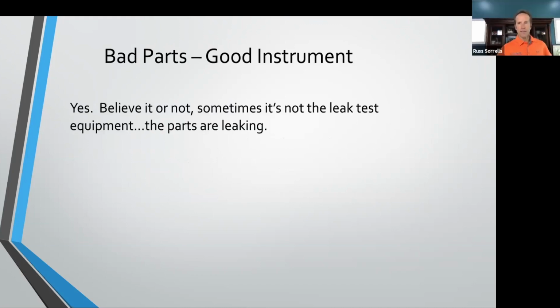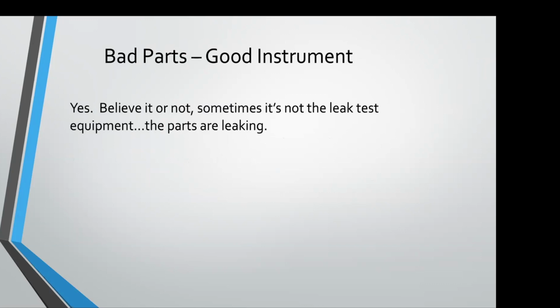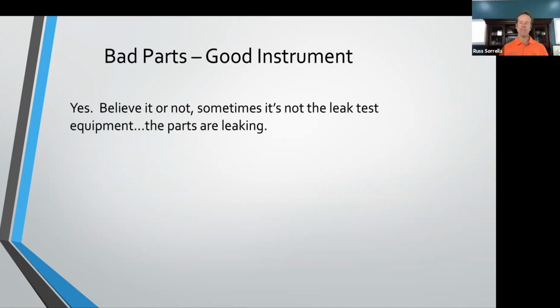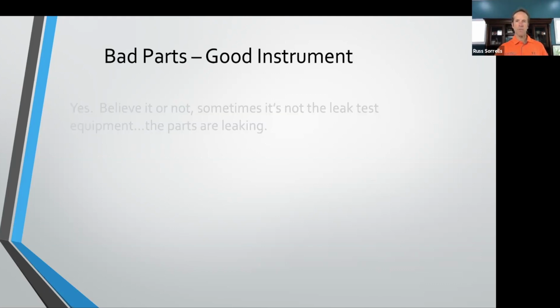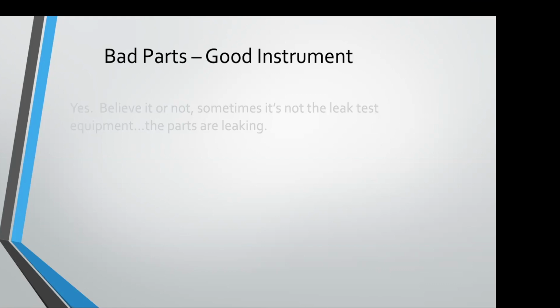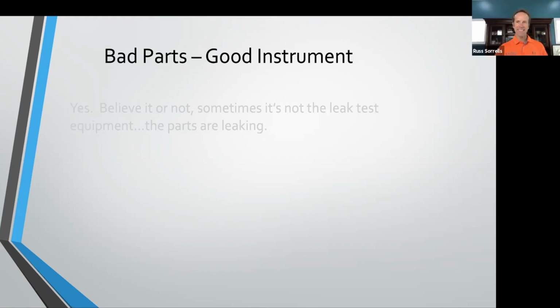Yeah, so this last one: bad parts, good instruments. Yes, believe it or not, sometimes it's not the leak test equipment. The parts are actually leaking. What we're working to do all the time, and I know you as well, Gordon, is build confidence with our customers in the equipment itself. When you have that confidence, the operator is no longer pointing to the instrumentation. They have the confidence to say, this is a bad part, I know it's a bad part. That's always what we're working toward. Anything to add, Gordon? Oh, everything leaks. That's right, and leaks are not repeatable.